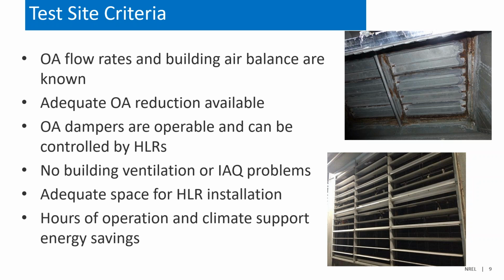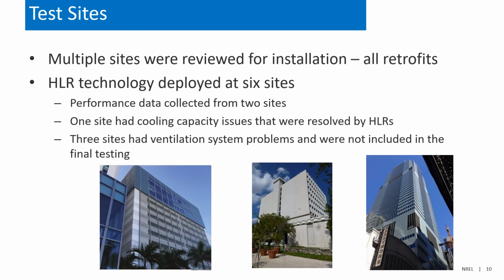In some cases, the HLR can actually relieve some of those IAQ problems, depending on what it is. Obviously, you need to be able to install this, so you need space and access to the return air ducts if you're doing that. And you have to have enough hours of operation and the climate to really give you the energy savings that you're looking for. We'll talk more about that. So we looked at multiple sites, and all were retrofit opportunities. So we ended up deploying this at 6 different sites. We were able to collect performance data at 2 sites. One site had capacity challenges, so unfortunately we couldn't establish a baseline, but we were able to show significant improvement in overall performance of the building. So we'll talk about that as well.